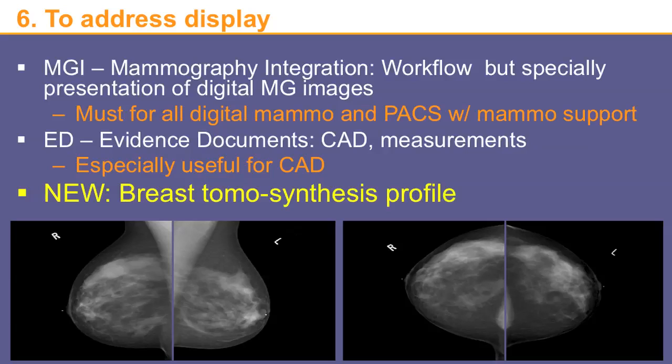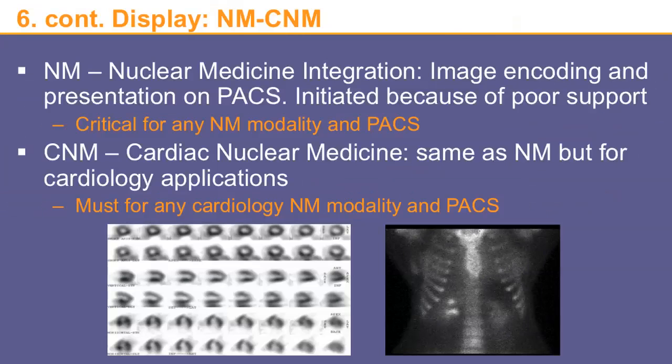However, if you say that you support the IHE profile for viewing mammography, then you can expect the images being displayed exactly as shown in this slide and exactly as the radiologist wants them to be displayed. If you now have computer-aided diagnosis or CAD marks, you also want them obviously displayed correctly, and that's also defined by IHE in another profile called evidence documents.